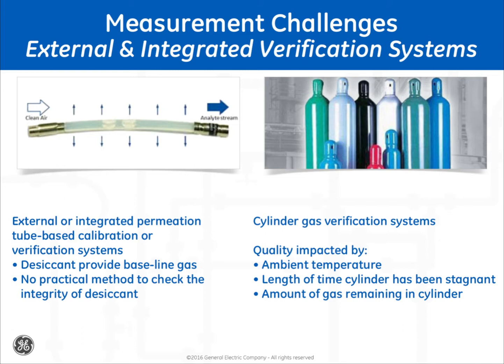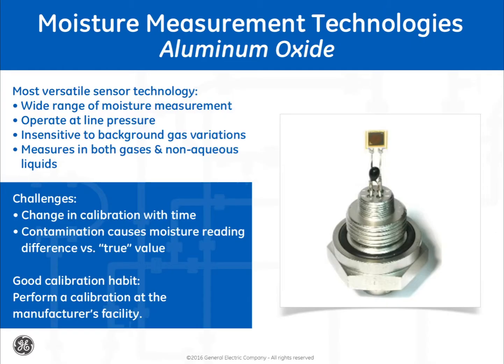Let's take a moment to recap what we've covered. We understand that the water molecule offers measurement challenges. The moisture sensor and analyzer are only one or two components in the complete measurement system. Verification and calibration can determine if or where there may be a measurement problem, and we have identified several methods of field verification, along with the challenges these techniques may offer in the field. Now let's look at some of the moisture measurement techniques. For each, we will look at the importance of the calibration and field verification.